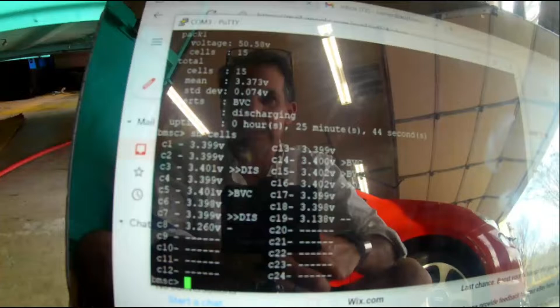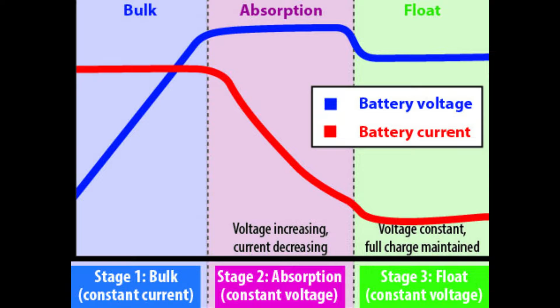We can see that almost all the battery cells are at 3.4 volts each. This means we're in the final stages of the absorption charge, charging with a constant voltage while current decreases until it peters out. Current decreases until it reaches 0 amps for two reasons: one, the battery's capacity to store charge is saturated, and much like a capacitor, current asymptotically approaches 0 as the charge saturates. Two, even if the batteries aren't saturated, as the voltage of the battery pack nears the voltage of our charging supply, those values equalize and current stops flowing from high electric potential to lower electric potential.